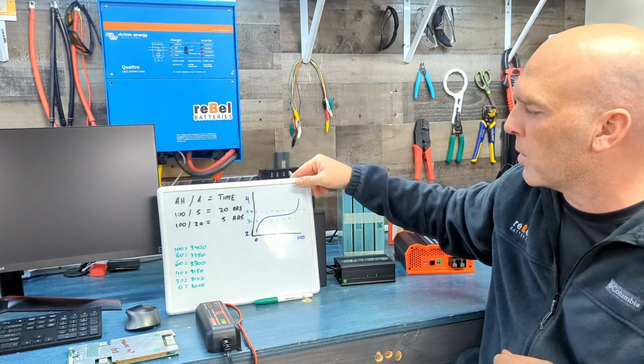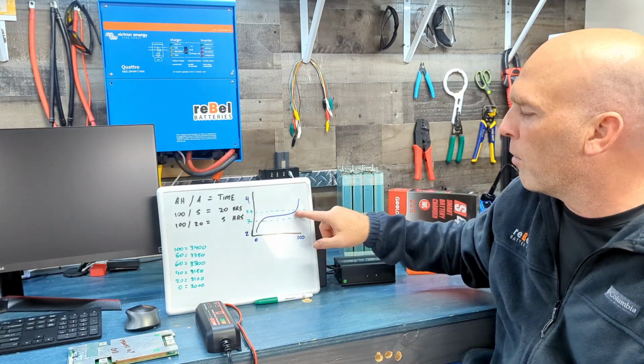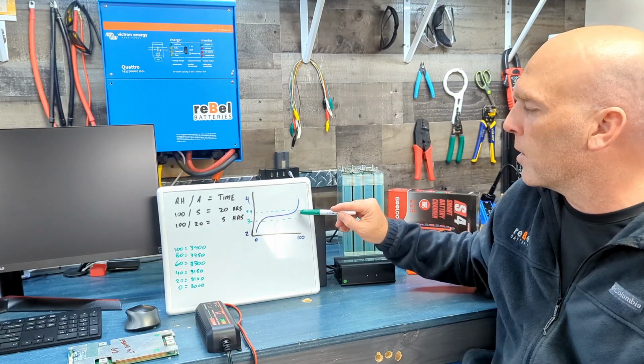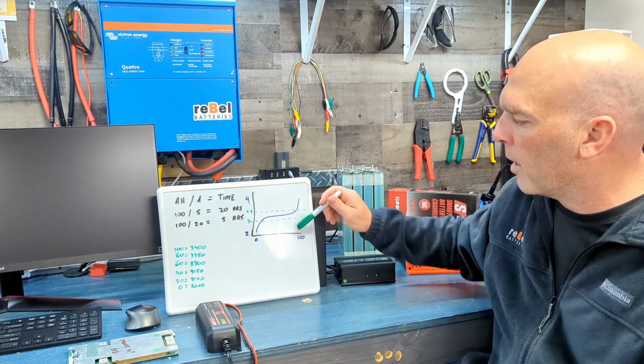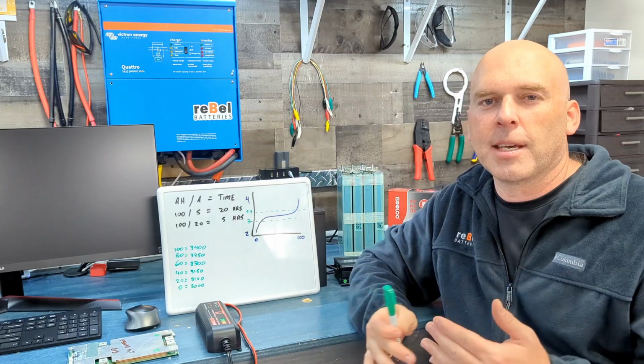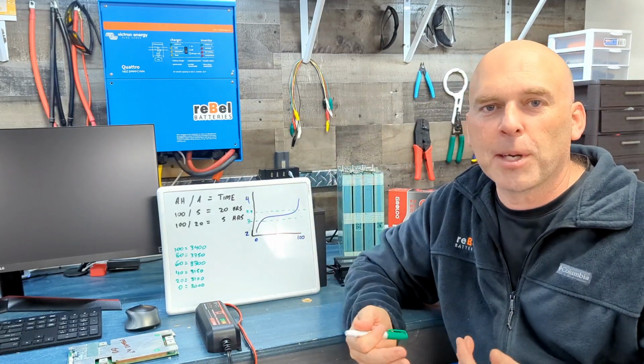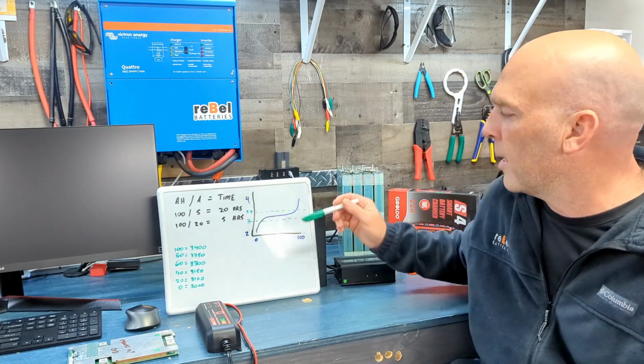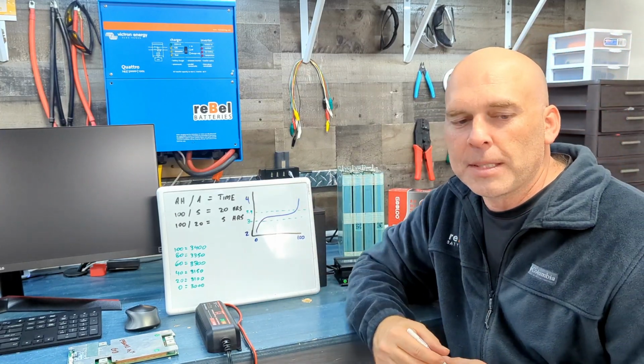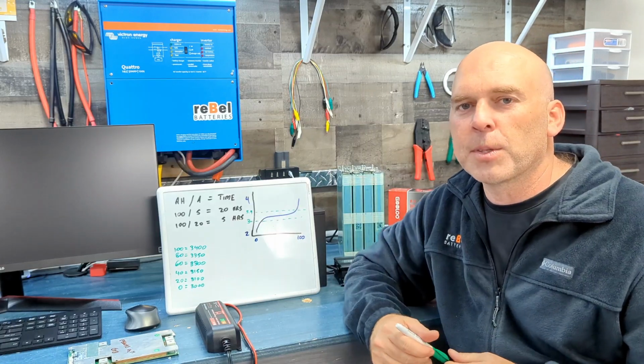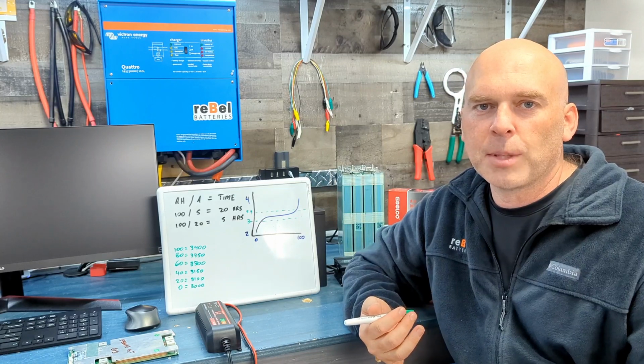For absorb and float, kind of the same idea. Absorb, say 13.8 plus or minus about 0.1. The idea is you're dropping the voltage down so you can get a bit more capacity at the end, because when you're ramming high voltage and high current in, the cells spike up fast on their charge curve. This is a typical charge curve for a lithium cell. Near the end, if you've got high voltage and high current going in, it shoots up quickly. But if you switch to absorb, it slows down and you get a bit further into the 100% range. That's why you drop the voltage. So 13.8 plus or minus 0.1, doesn't need to be exact. For float, same idea, you're just keeping it out on this far end, so 13.6 should work fine. You can deep dive and research more, but those are the settings: 14.2 to 14.6 for bulk, 13.8 for absorb, and 13.6 for float.